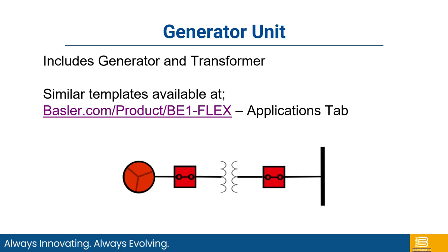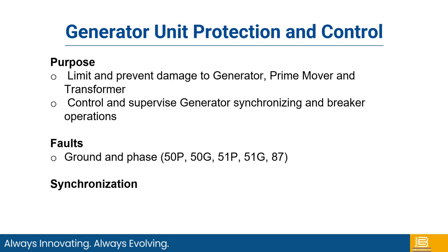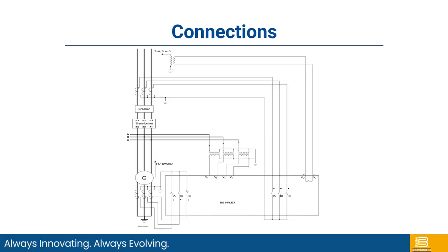Next example is a generator with a generator step-up transformer. Notice there is a generator circuit breaker and a high-side transformer breaker. This limits and prevents damage to the generator, the prime mover, and the transformer. You can control and supervise generator synchronizing and breaker operations. You can also do instantaneous phase overcurrent, ground overcurrent for both instantaneous and time overcurrent plus differential. And it can also do synchronization.